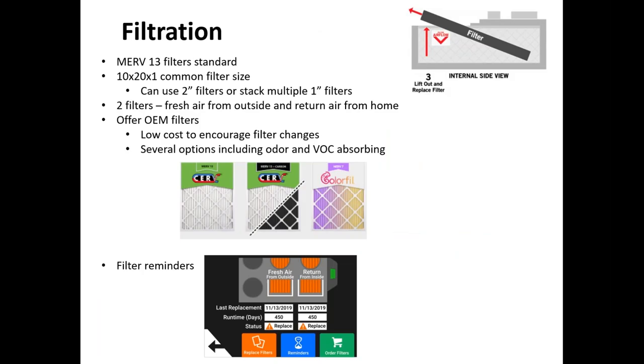Some features and options of the unit. The filtration is something that is important in maintaining air quality as well. So you want to filter particulates. The system uses standard 10 by 20 filters. They're MERV 13, 1-inch thick. We wanted to design the system to make filter changes easy and inexpensive, to encourage them as often as possible. These are just standard sizes you can buy locally or online as well. The system can also accommodate thicker 2-inch filters, or you can stack multiple 1-inch filters to get the filtration level and features that you'd like.